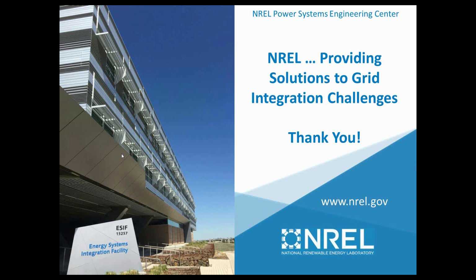The challenges that I've heard people have with it is that it's something that would have to be embedded in distributed generation, so it's adding a little bit of cost, but obviously probably much less than a dedicated fiber line. And you'd have to make sure that the utility really is able to provide that signal without causing undue distributed generation trips, because now everything has a permissive signal to be connected. And so potentially you may have some issues with the ability to massively trip everything off simultaneously. So there are some things that people need to think about.